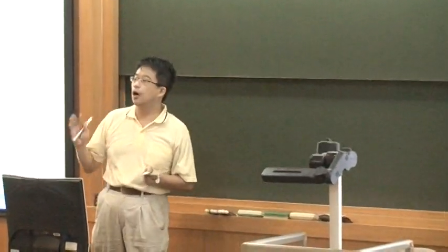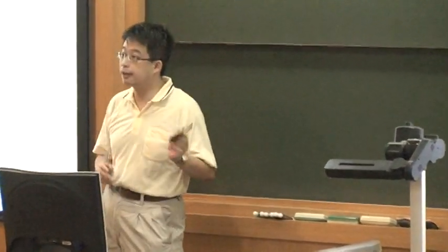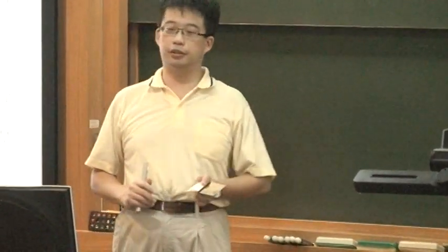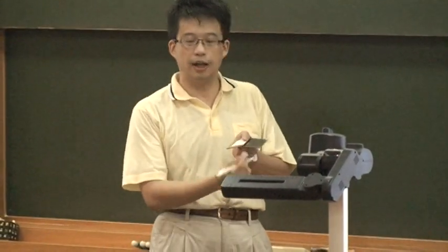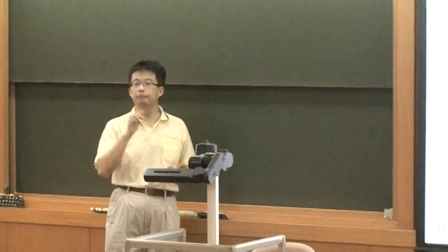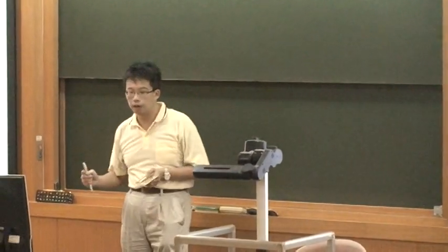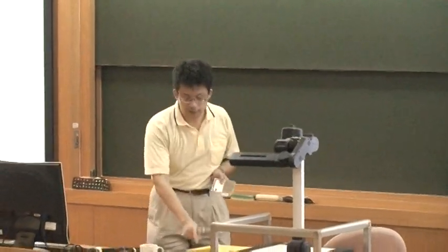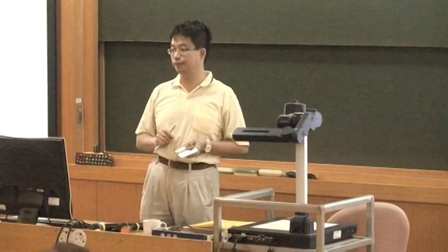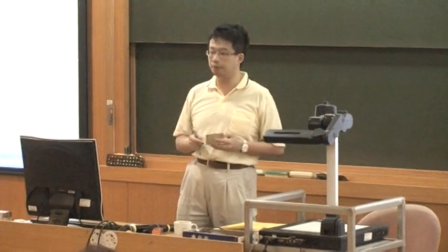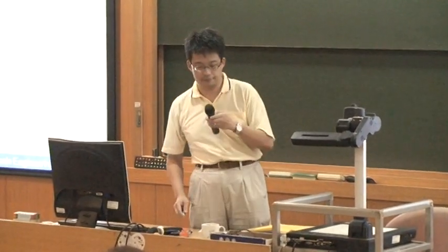So it's just like an optical lever, magnifying the position change of this tip. So if I put the tip at one end, even if it moves a little, quite tiny, the signal will change a lot. So I can magnify the position and reversely tell the profile of this nanoscale box. So that's the principle of AFM.